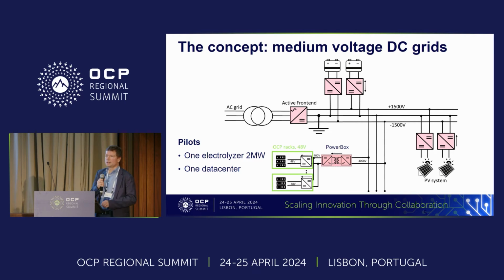Now we have this medium voltage grid of 3 kilovolts, and we distribute this in the data center. I showed here just one power box. So there's one power box which takes the 3 kilovolts and puts this down to 400 volts DC, which is a normal handleable voltage level, which then can be used by the power shelves in the racks.